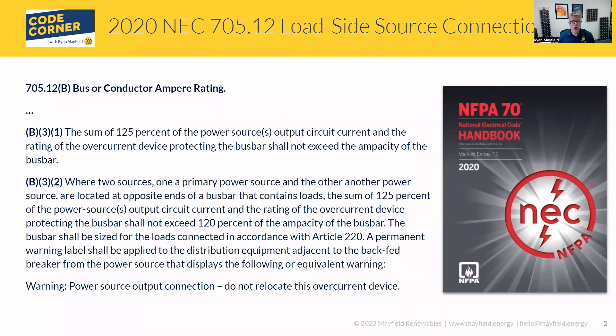So let's first look at the language in B31 and B32. B31 is one that's probably not actually used all that often — it's kind of a hard one to have a system that meets this requirement, but there's an allowance for it, so we'll go through it. B32, this is the one that is lovingly referred to in the industry as the 120% rule. It's very, very typical way that systems are interconnected, especially on residential systems.